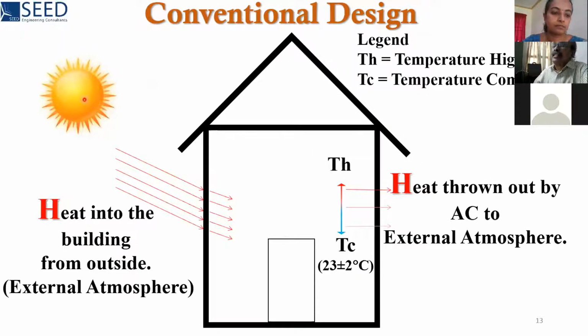Because solar energy, the sun's energy, by the normal process of conduction, convection, and radiation is transmitted into the room. Thereby its temperature is elevated to a high level, represented here by the letter TH, which is temperature high. This is not comfortable for the human beings occupying that room. So we have to somehow bring it down to TC, which is normally considered as 23 plus or minus 2 degrees centigrade, termed as temperature comfortable. How do you do that? We do that by throwing a portion of the heat energy to the external atmosphere.